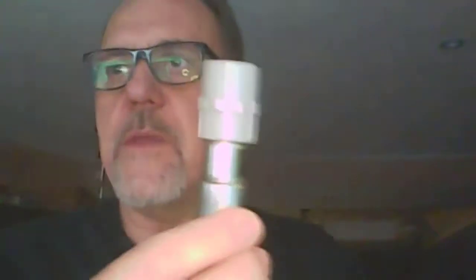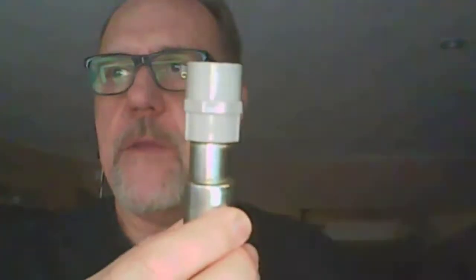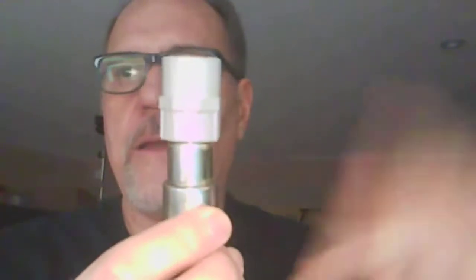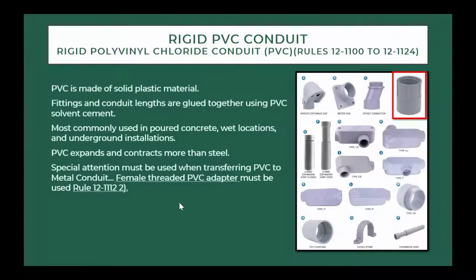Come back in a year or two, this will be cracked. If it's outdoor, it'll be cracked. There's no way it'll make it. It'll crack. So the right way to do it is to put this female adapter. Top 10 defect. People run PVC underground and then they run steel pipe up a wall or something like that. They forget to put this piece here.